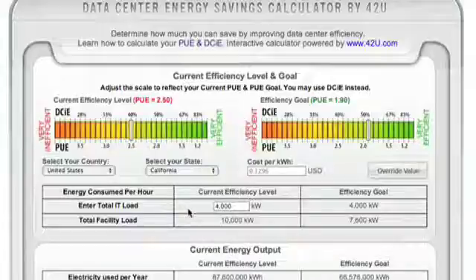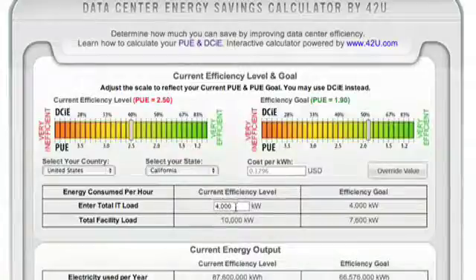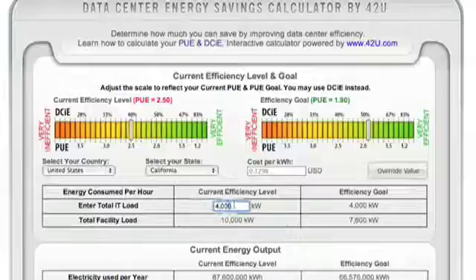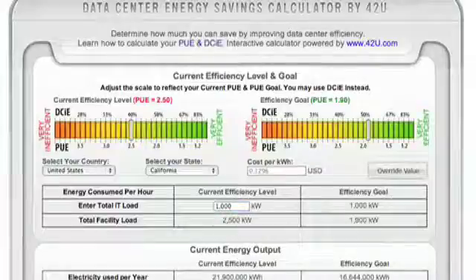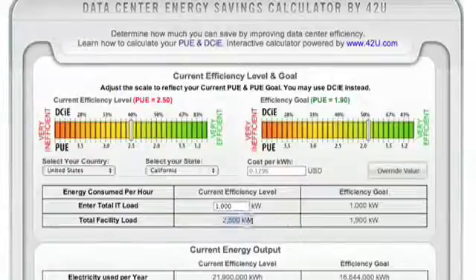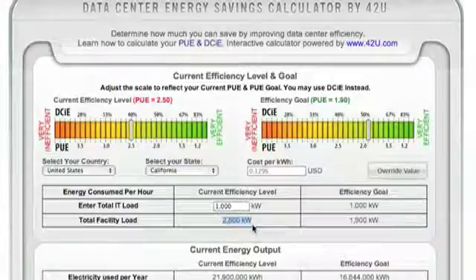Now the total IT load is perhaps most easily accessible from your UPS. In the event of a power outage, this is the total load your UPS is required to support. For simplicity's sake, we'll input a total IT load of 1,000 kW, or 1 megawatt. After entering 1,000, you'll notice that the values under current efficiency level have changed. The total facility load changed to 2,500 kW — 2,500 divided by my 1,000 kW IT load produces the PUE of 2.5.